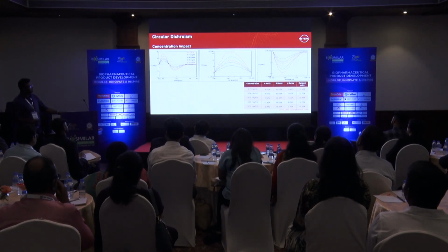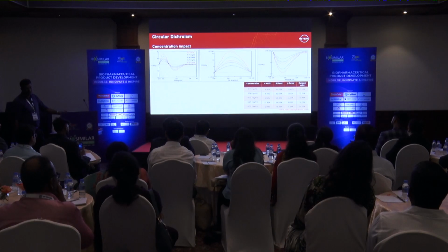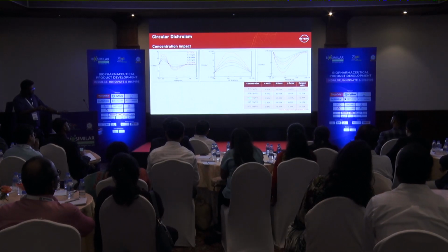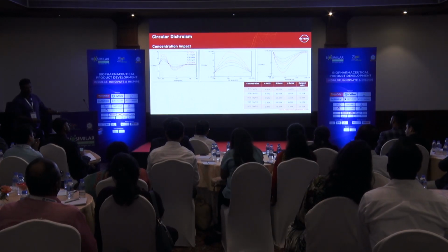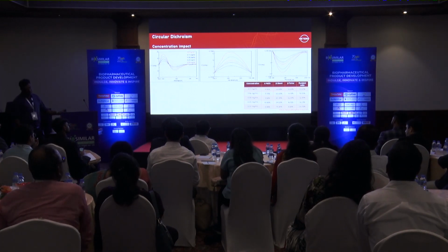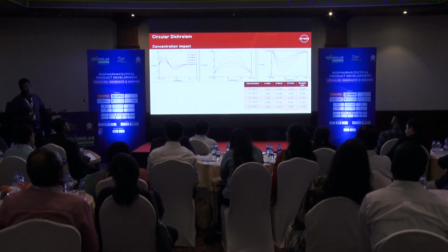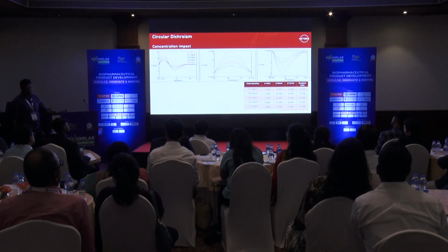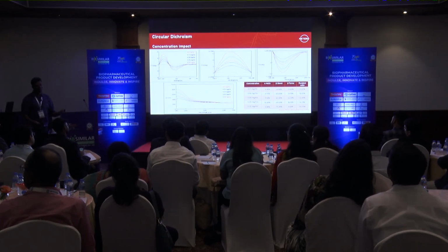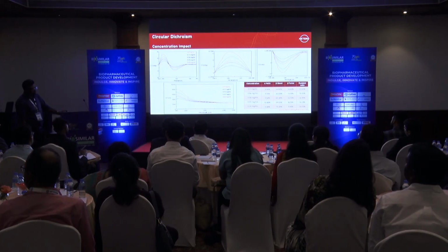But again, when you quantify, you start seeing a difference in the alpha, beta values assigned by the software. If you see closely, there is a certain saturation point, a concentration above which the values become erroneous. This is a very important aspect when we are developing a CD spectra, which is known as the photomultiplier tube voltage, the HT.